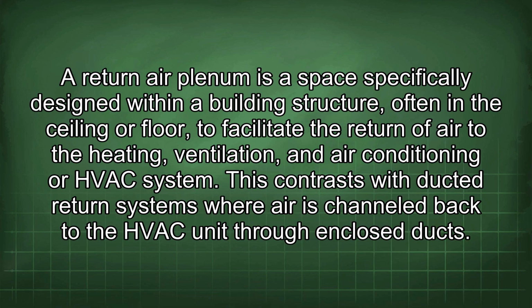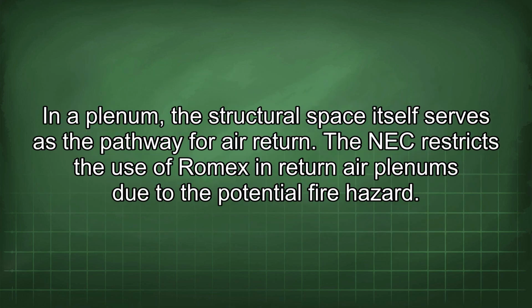A return air plenum is a space specifically designed within a building structure, often in the ceiling or floor, to facilitate the return of air to the heating, ventilation, and air conditioning, or HVAC, system. This contrasts with ducted return systems where air is channeled back to the HVAC unit through enclosed ducts. In a plenum, the structural space itself serves as the pathway for air return. The NEC restricts the use of Romex in return air plenums due to the potential fire hazard.